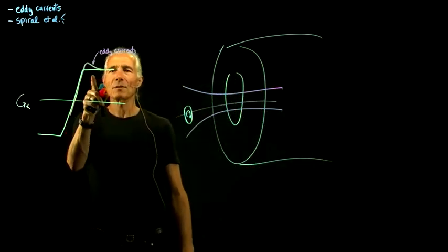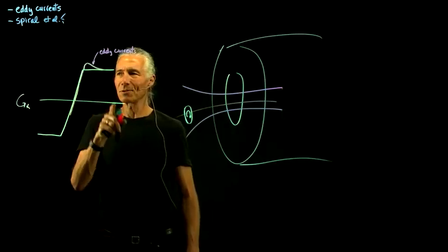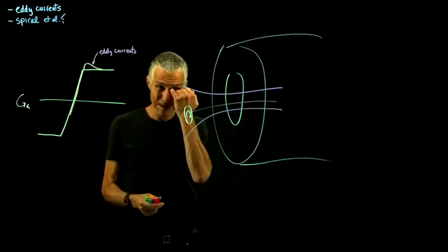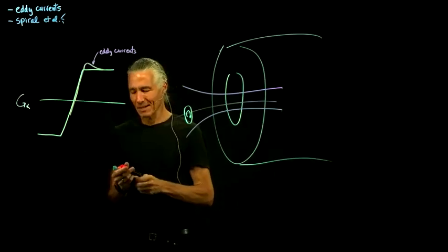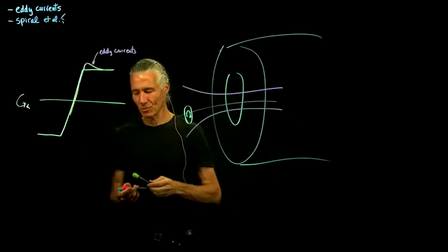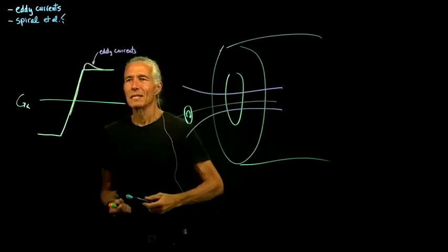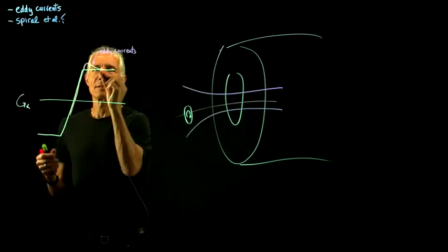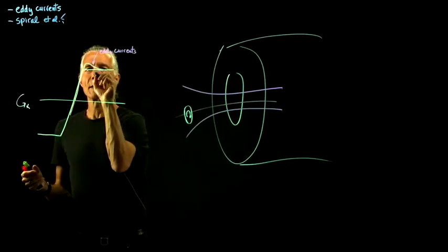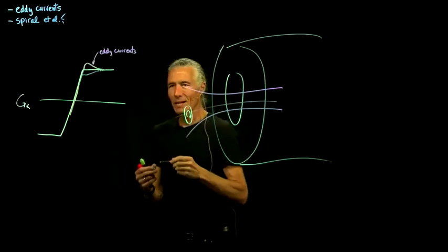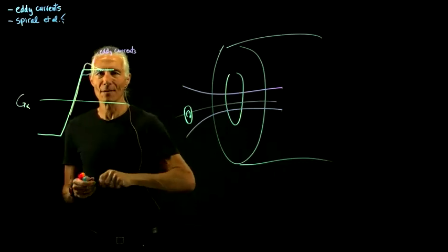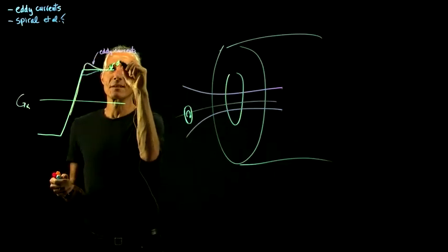And so this is well known that it doesn't do what you told it to do. And so there's a whole complicated system in there called eddy current compensation. What it does is it attempts to essentially compensate for that. This is what you asked for, so this is the desired.